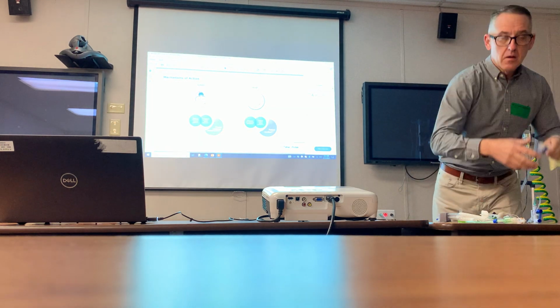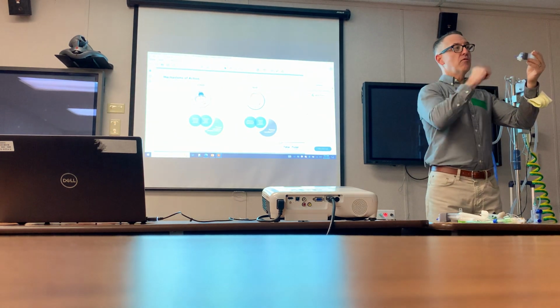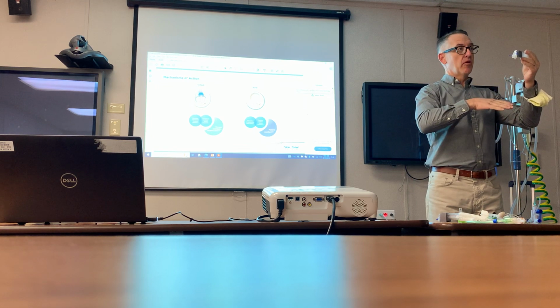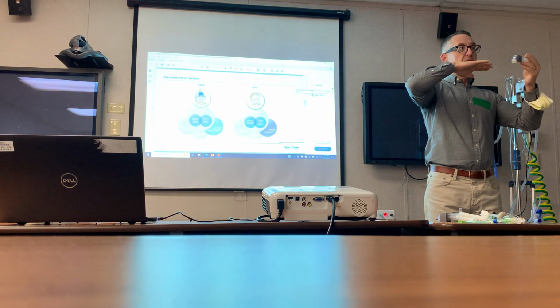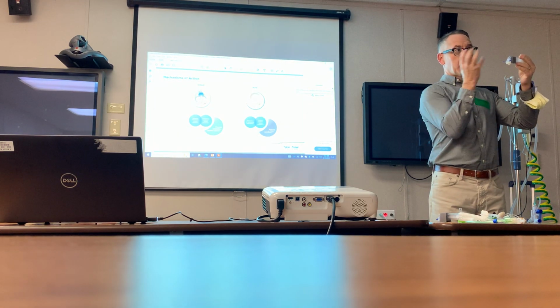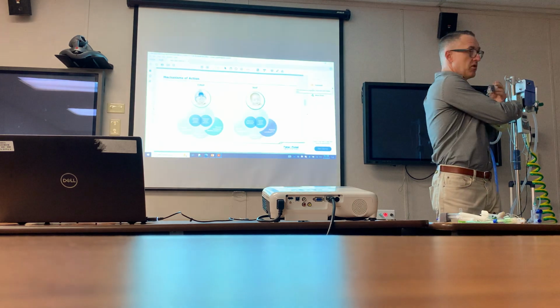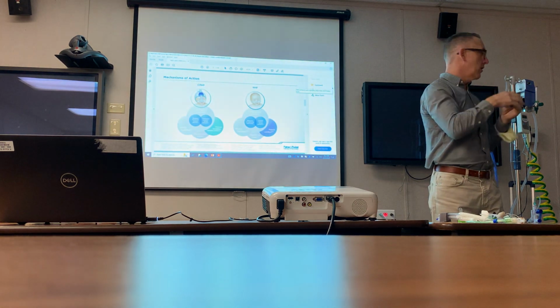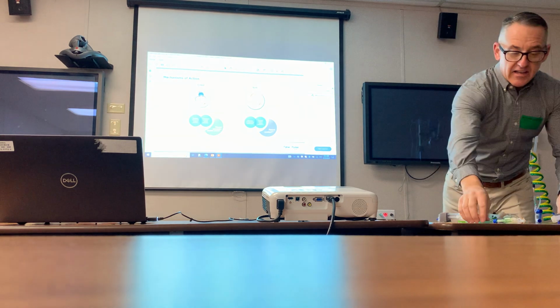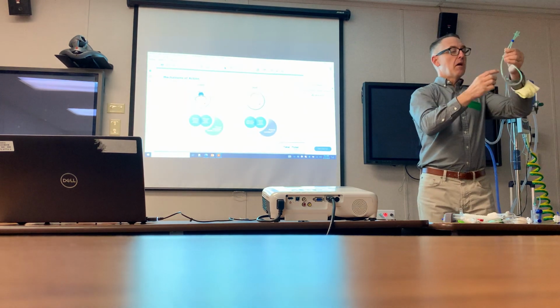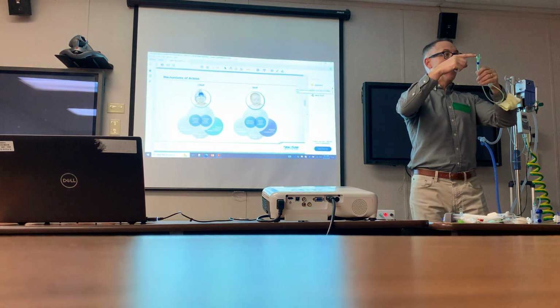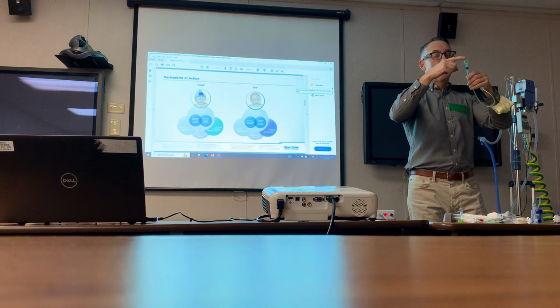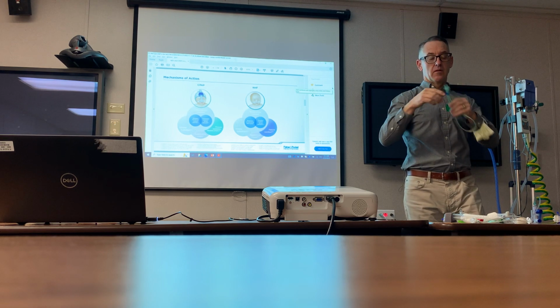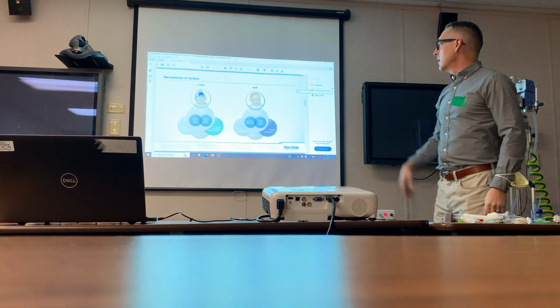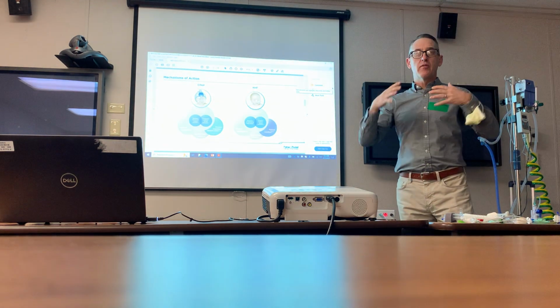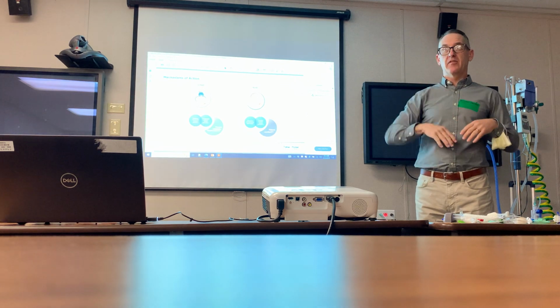But basically, when this interface is on, it will give you a reading when there's a stopping point where the air can't go any further, right? It stops basically if it hits the bottom of the lungs, the air creates a pressure, and now we've created a CPAP, and you get a reading that says, okay, the air is not going any further. This is how much pressure has been reached. In a cannula, just to get in front of it, it no longer is reading down here, it's reading back here, and that's why you're getting a false reading. We're actually going to see that visually, but we'll get to that in a minute. Okay, in nasal high flow, instead of looking for that specific pressure, we're just looking for something to wash out CO2, right? Okay.